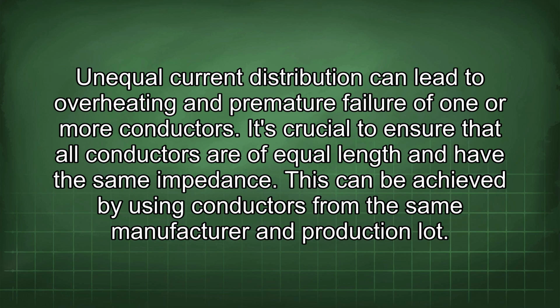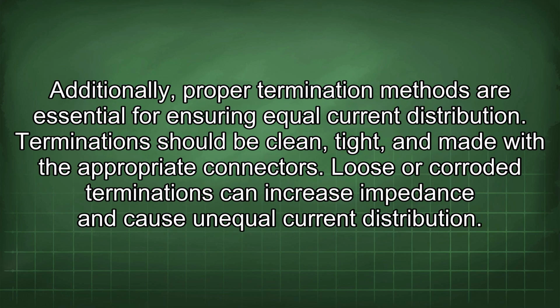It's crucial to ensure that all conductors are of equal length and have the same impedance. This can be achieved by using conductors from the same manufacturer and production lot. Additionally, proper termination methods are essential for ensuring equal current distribution. Terminations should be clean, tight, and made with the appropriate connectors. Loose or corroded terminations can increase impedance and cause unequal current distribution.